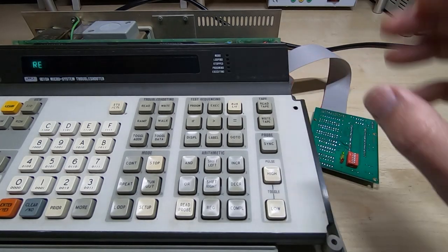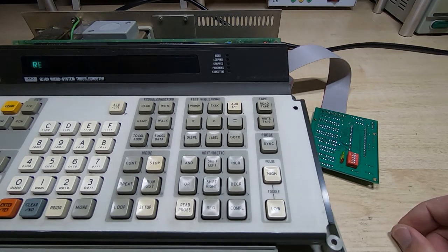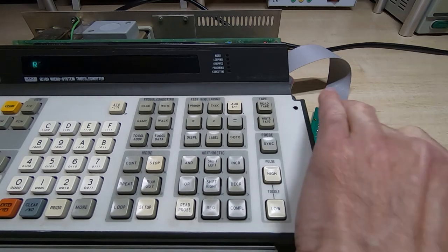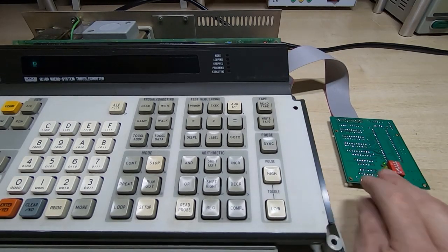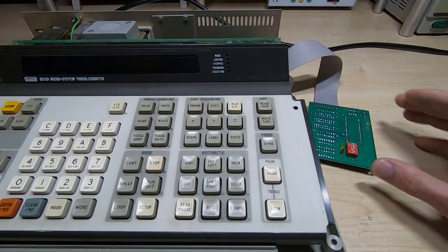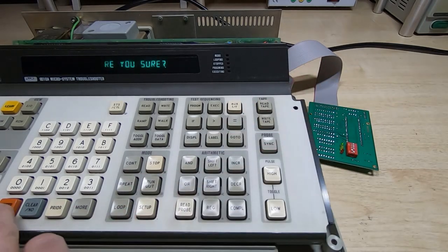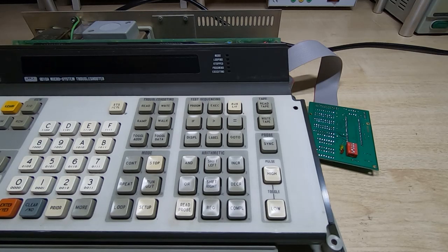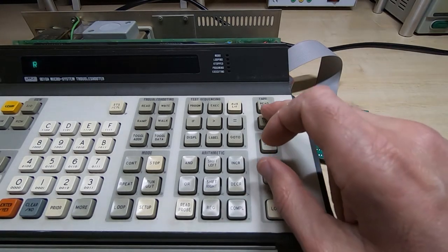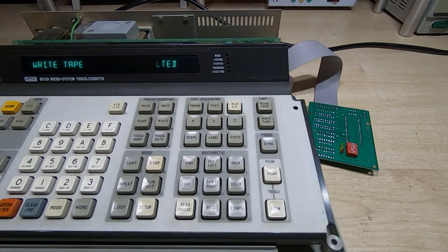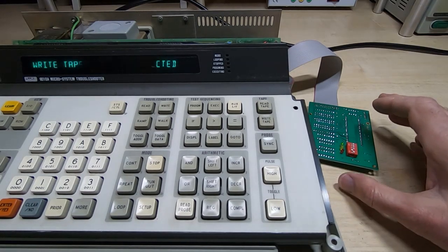Even if you have the RS-232, that's still a bit of a pain. Also, what you can do, of course, is switch the write protection on. So I've now got this set for write protect, so we can still read the tape when that's on. So it's reading the data, and that's now read. But if you try and write with the write protect on, then you'll get this write protected message. It just stops you overwriting if you don't want to.